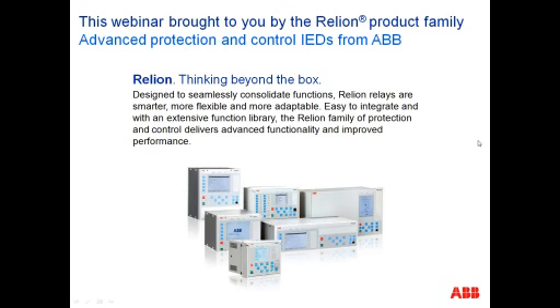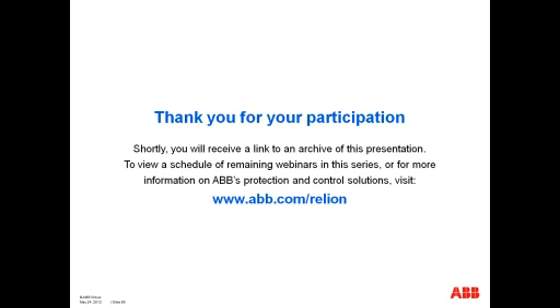In times past, electromechanical relays were used because electromechanical relays were discrete relays. You had zone 1, 2, and 3. The application of the whole other panel of zone 1, 2, 3 and pilot was not always used. But with the modern relays, you have a lot of stuff in one box. You can do a lot, but you need at least 2 boxes. And how you distribute the functions on them really depends on the application.